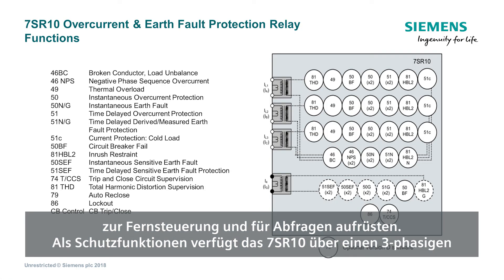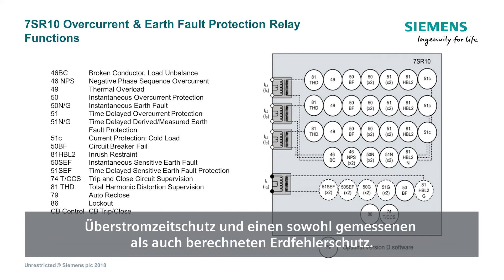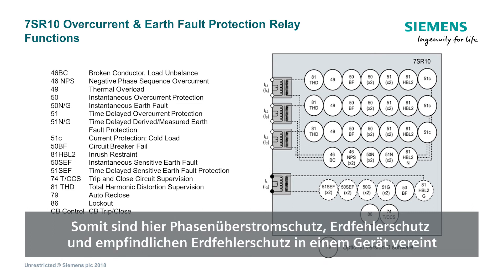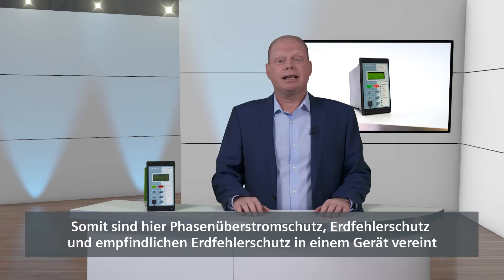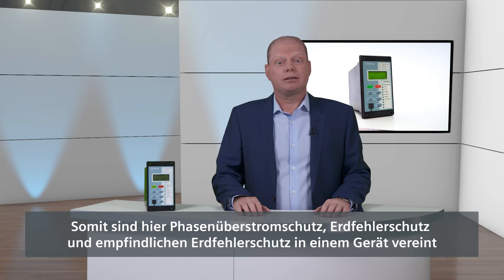In terms of protection functionality, the 7SR10 provides three phase overcurrent and both measured and calculated earth fault. Therefore the relay can provide phase overcurrent, earth fault and sensitive earth fault in one device.